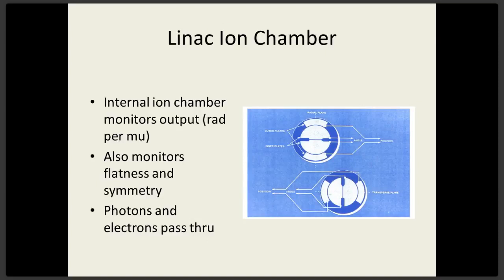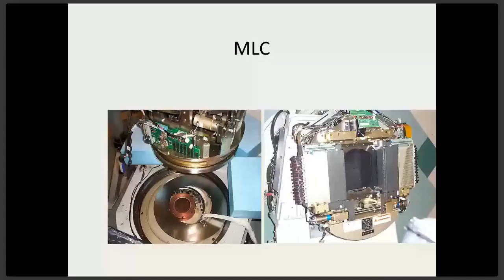The ion chamber, very important device. Not only does it measure the output of the machine, but it also measures symmetry and flatness, which are two important characteristics of the radiation beam. And the way it does that is by splitting the ion chamber in half and comparing the top half to the bottom half and the left half to the right half. So there's basically 4 quadrants being monitored by the ion chamber, giving feedback to the linear accelerator about how symmetrical that beam is.